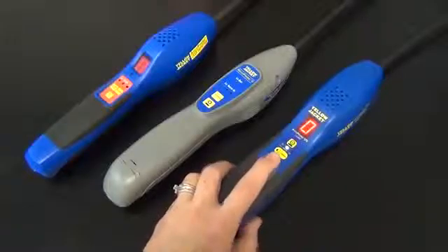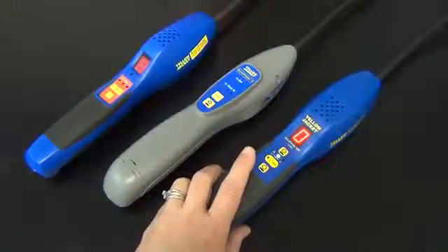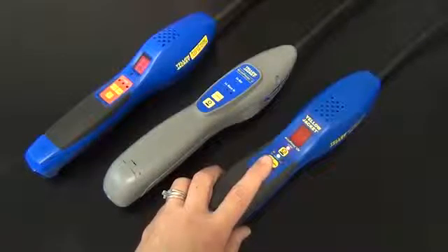The AccuProbe UV, again without the sensor, will still turn on. But what will happen is it won't come out of the warm-up mode. Take the sensor, make sure it's pushed on all the way — and it comes out of warm-up.